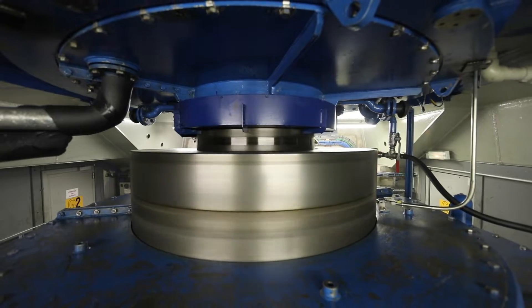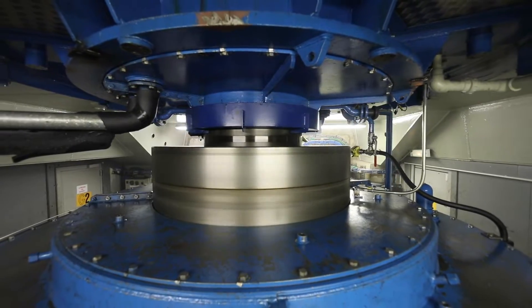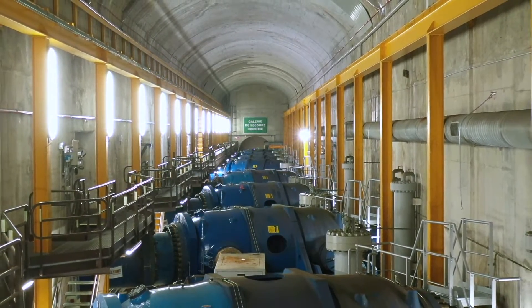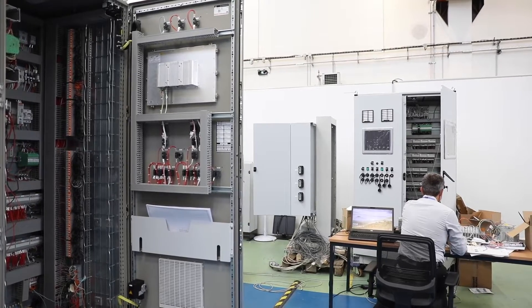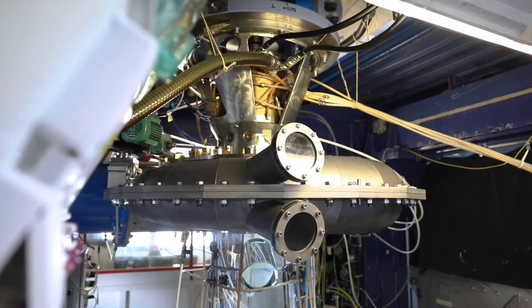GE performed two test campaigns on site at Grand Maison. Key mechanical components on rotating units as well as waterway flows were investigated during the trials. The turbine and pump behavior were excellent — no adverse effects or issues were detected. The operation of the units in hydraulic short circuit was monitored from minimum to full power in the most critical configuration, in order to assess the full range of flexibility. All results give us confidence that hydraulic short circuits at the Grand Maison scheme can become an industrial operating mode.